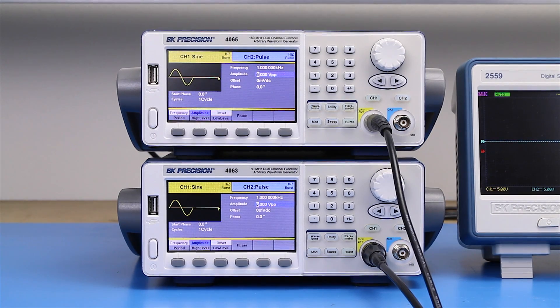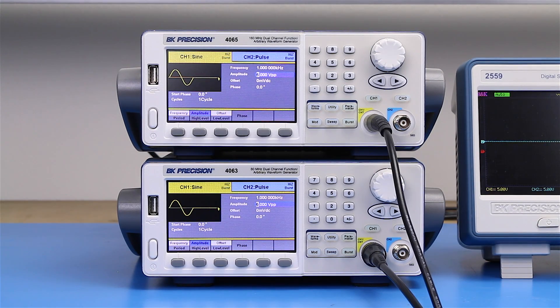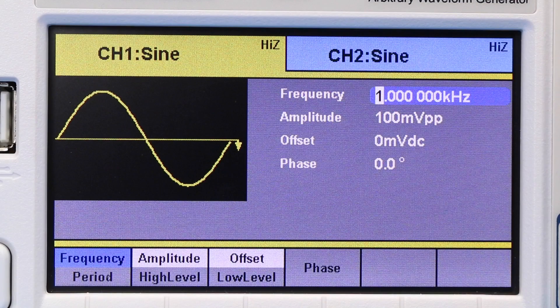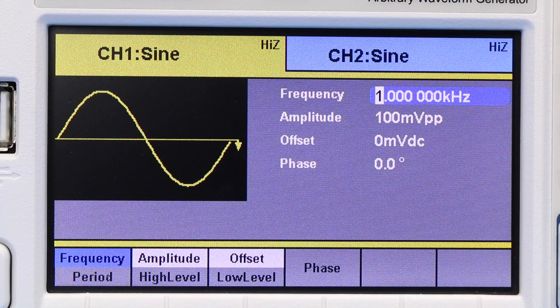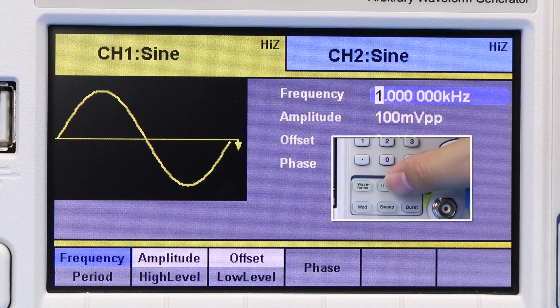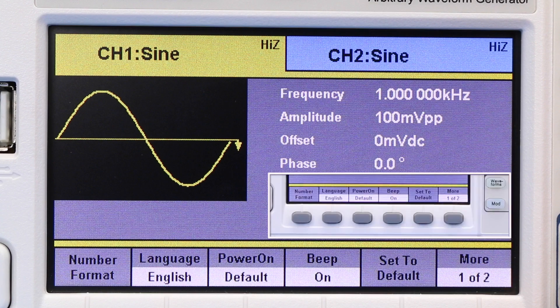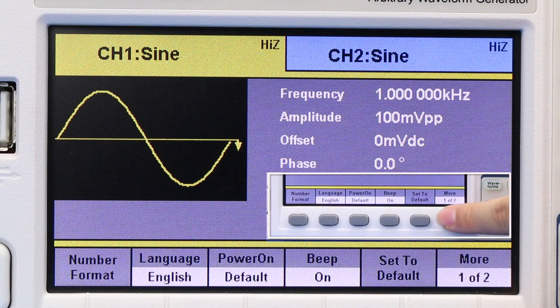For this example, we will use one of the generators as the master timebase. On unit 1, set clock source to internal in the following menu. Press utility, system, clock source.